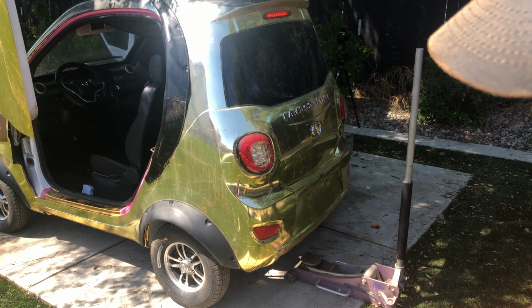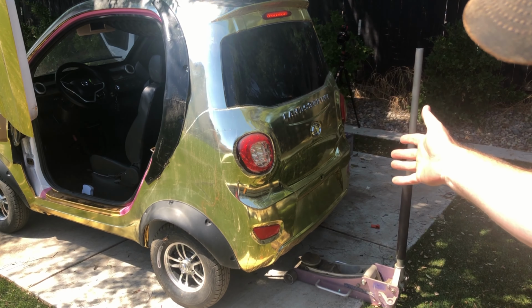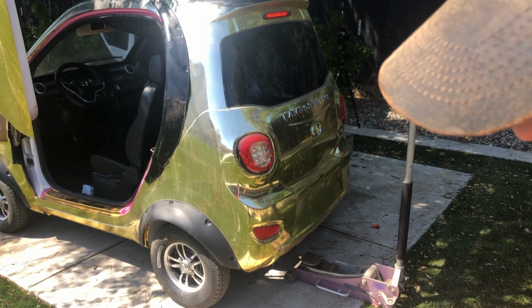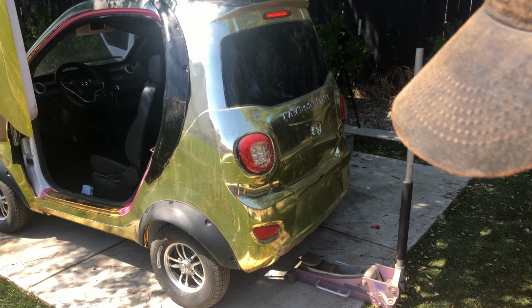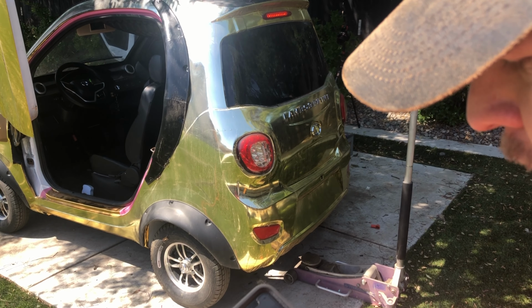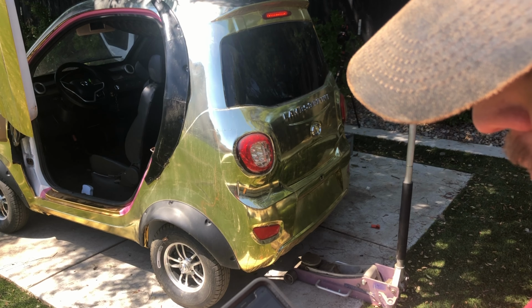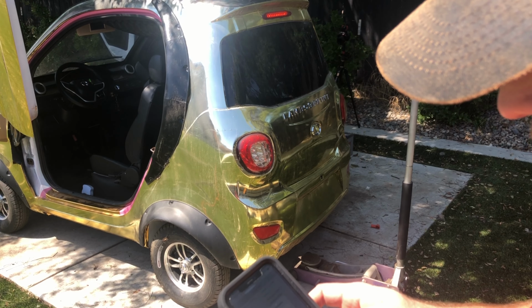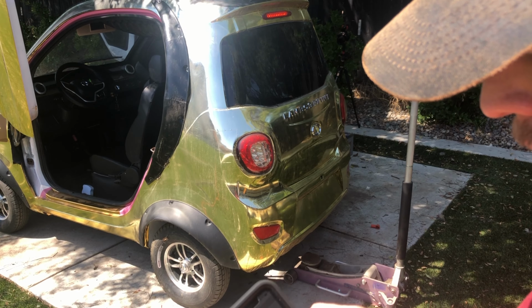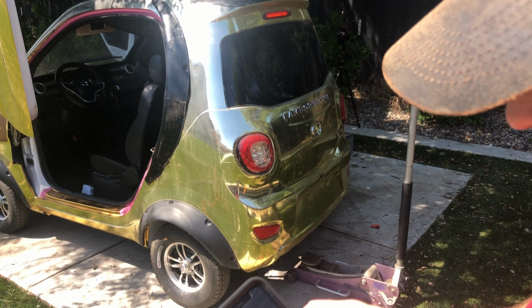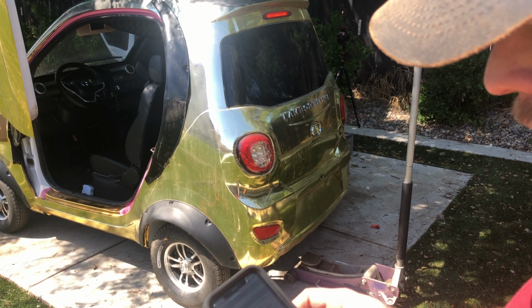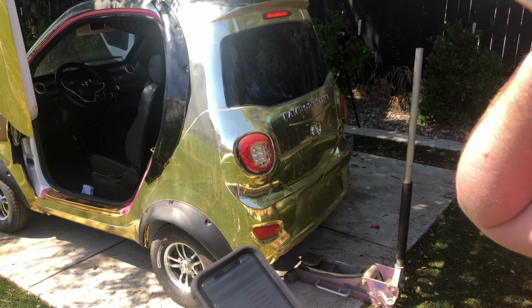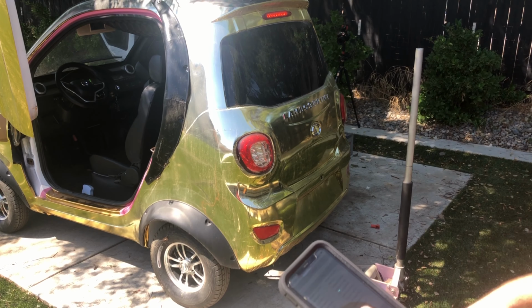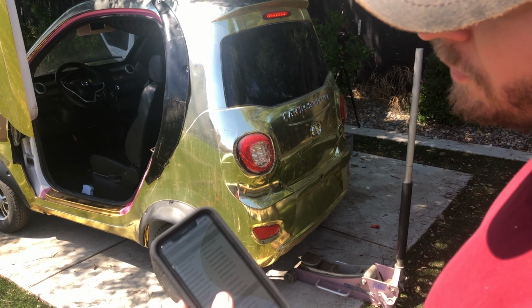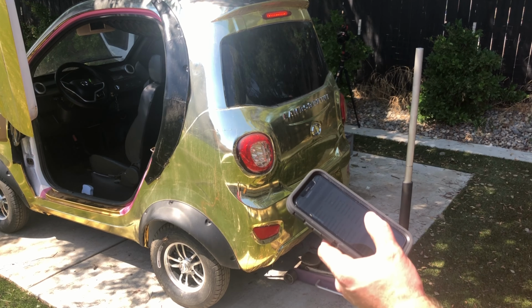Alright, that was a very clunky auto learn. It obviously worked to some degree. I'm going to try doing a cap on the maximum — I'm going to put a maximum speed not at 12,000 but at 4,000 for now. We're going to try auto learn one more time, because it was going up to like 5,500 and this motor is not rated for that. It's like 3,200 is what it's rated at. So we'll put it a little lower and see if we can get a better auto learn.